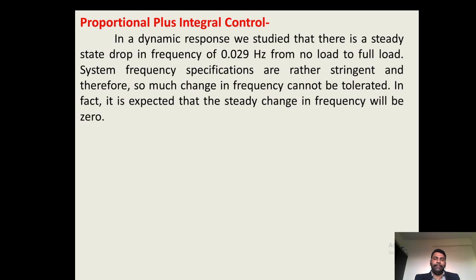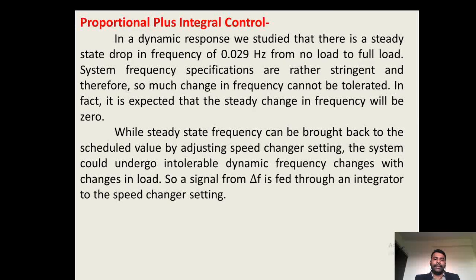We will start with proportional plus integral control. In a dynamic response, we have studied that there is a steady state drop in frequency of 0.029 Hz from no load to full load. The system frequency specifications are rather stringent, and therefore so much change in frequency cannot be tolerated. In fact, it is expected that the steady state change in frequency will be 0. This steady state change in frequency can be brought back to the schedule value by adjusting the speed changer setting.